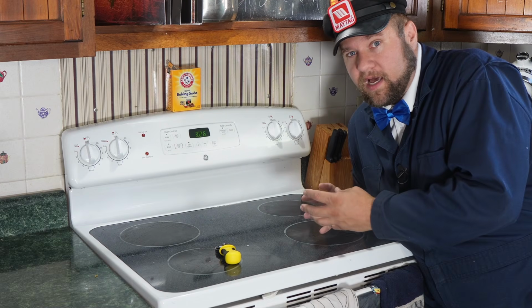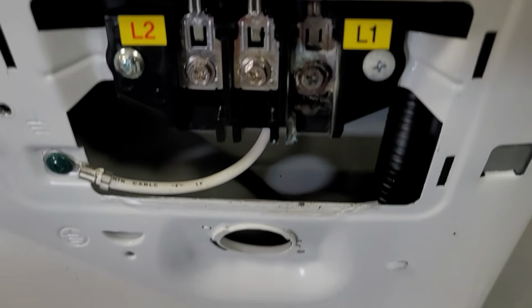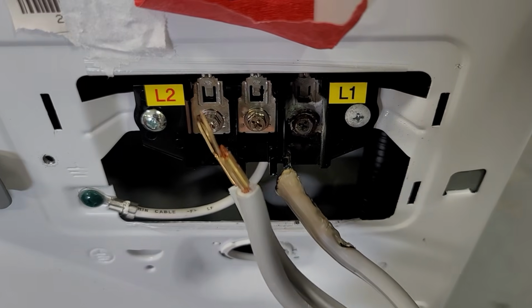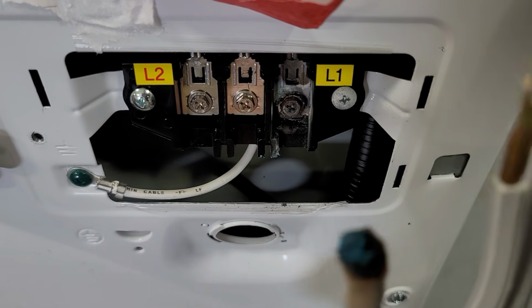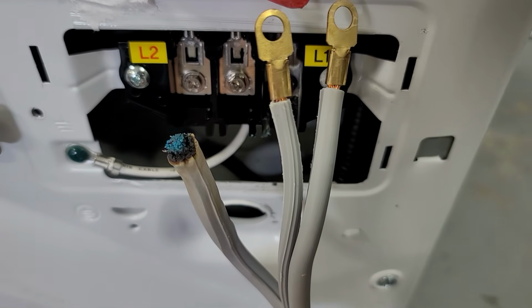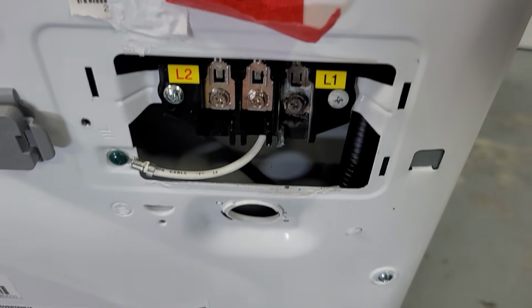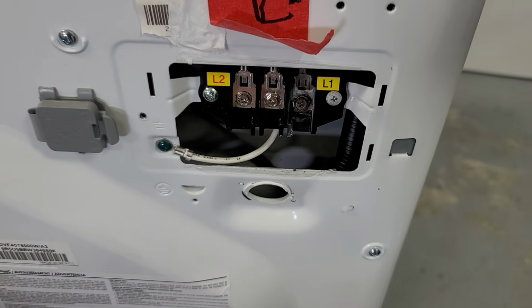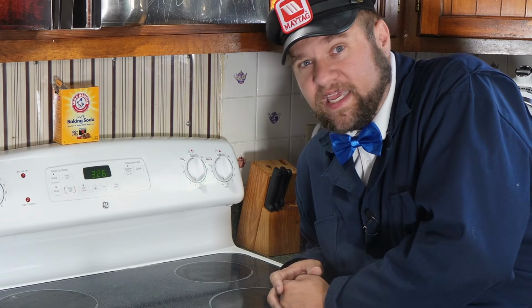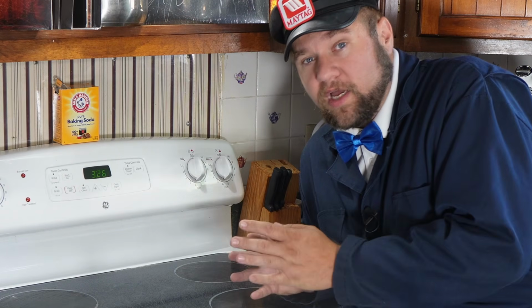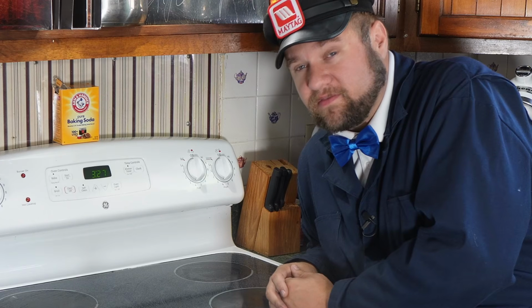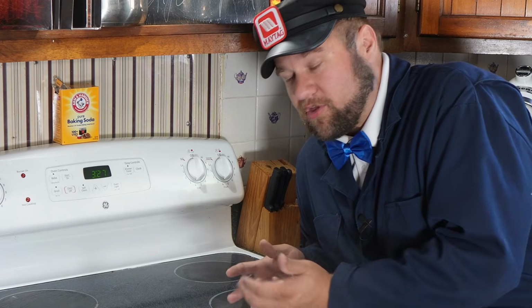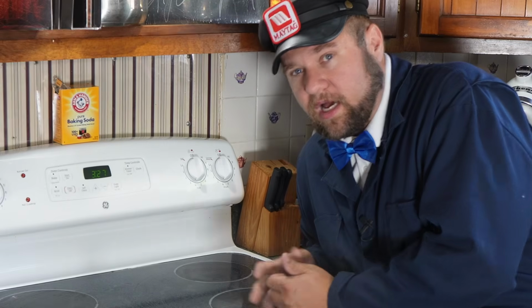If the cord and the nuts connected to each other end up separating, it will cause the connections to heat up over use as they slowly separate. This can eventually cause too much strain on the connection, resulting in the cord, terminal block, or both, and the wiring getting melted. The service call to fix that can be very expensive, as opposed to the $3 to $5 strain relief that generally comes with most power cords when you buy them new.